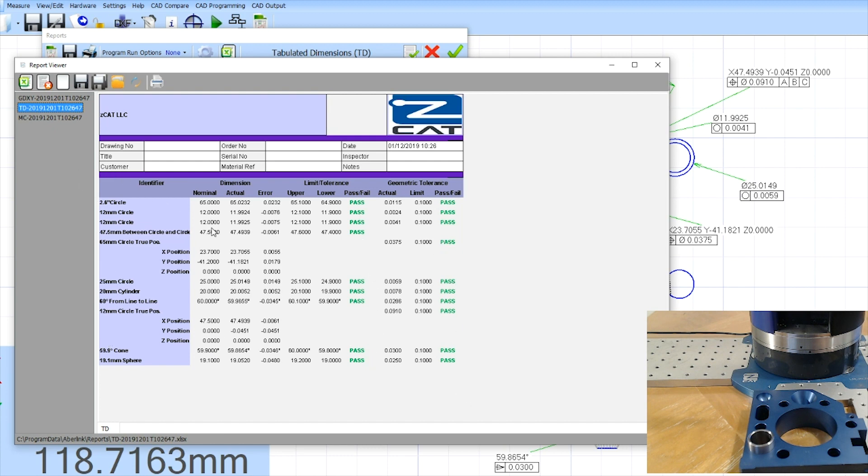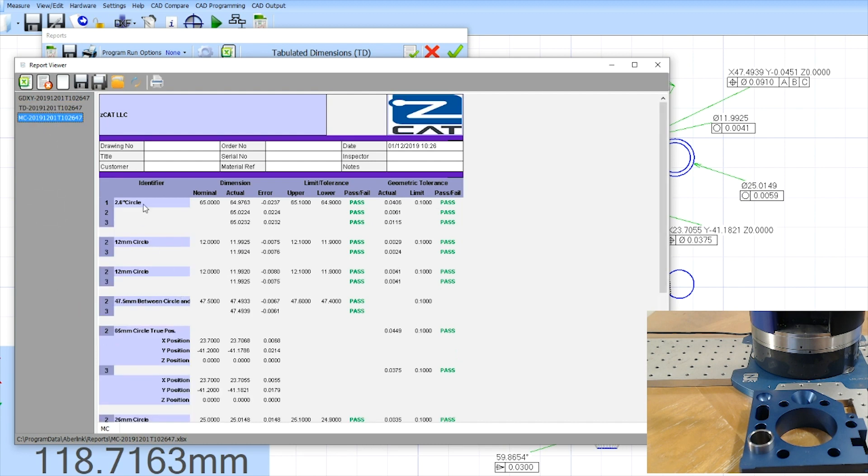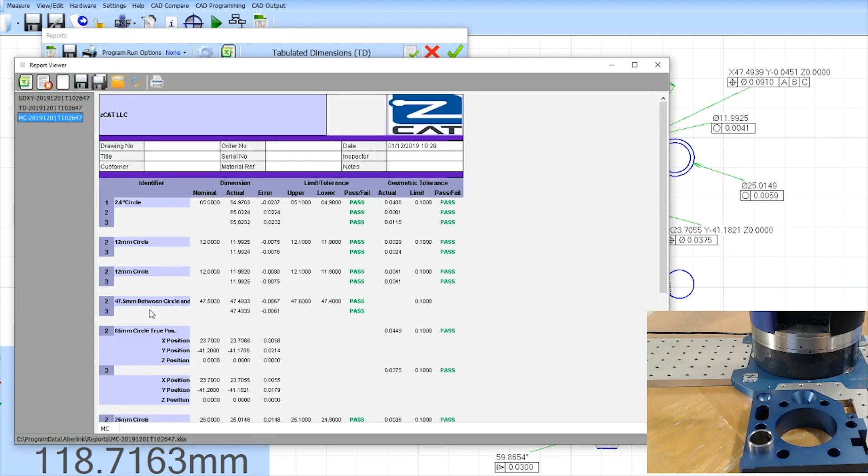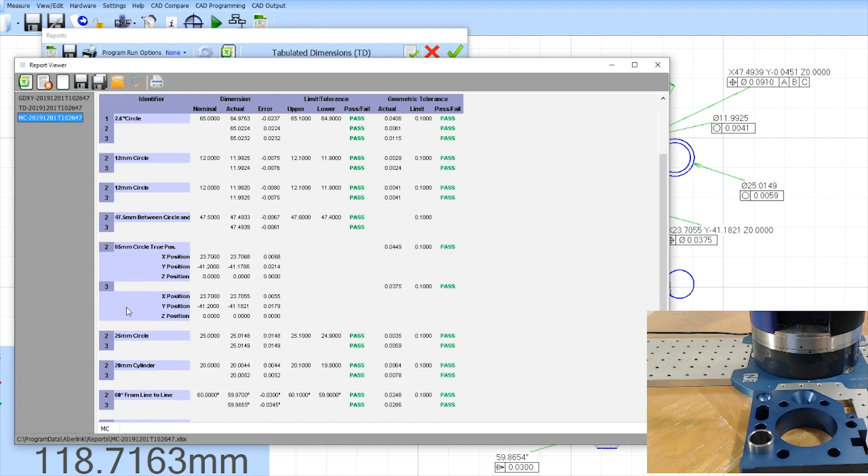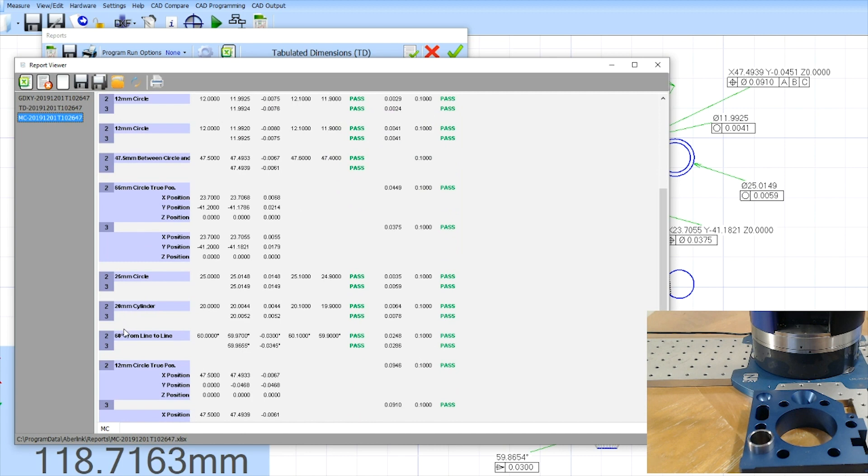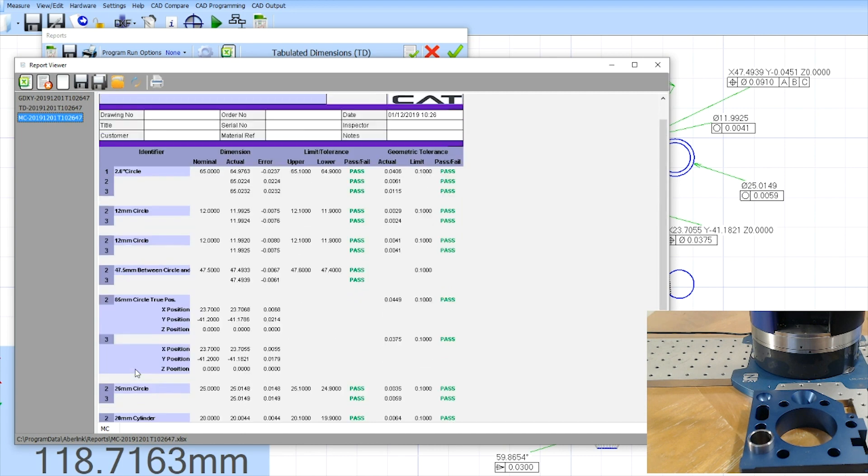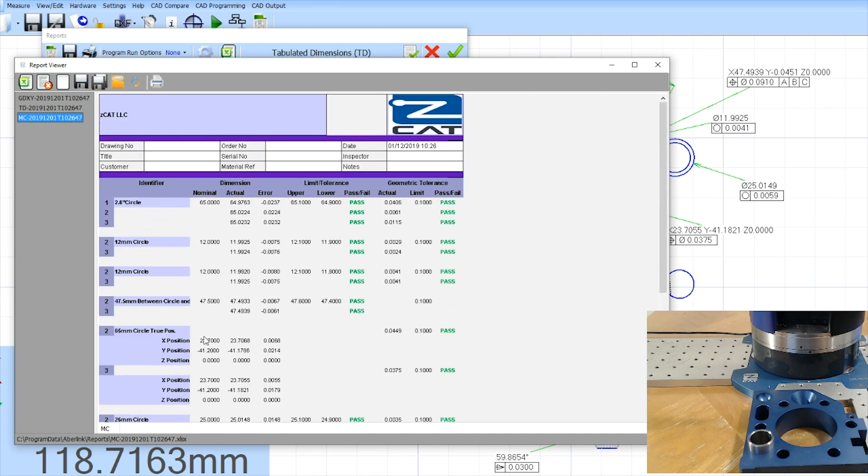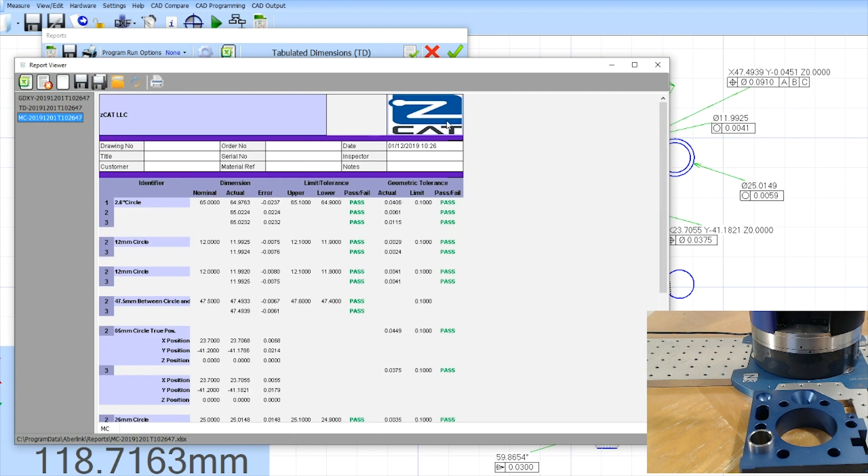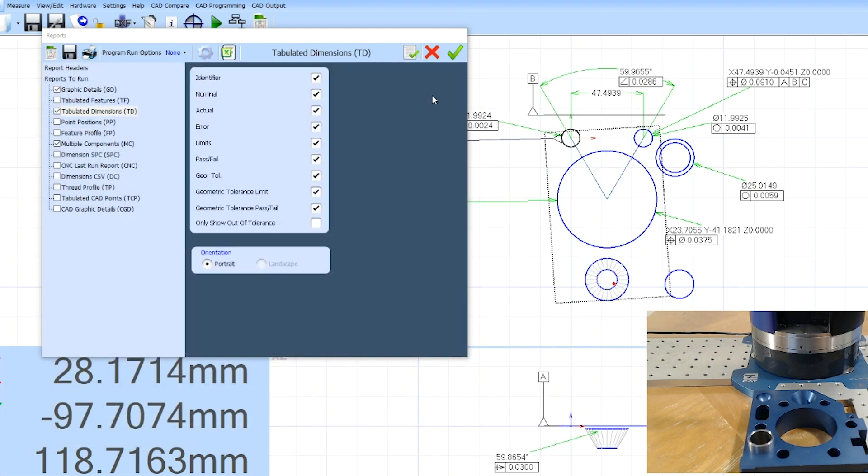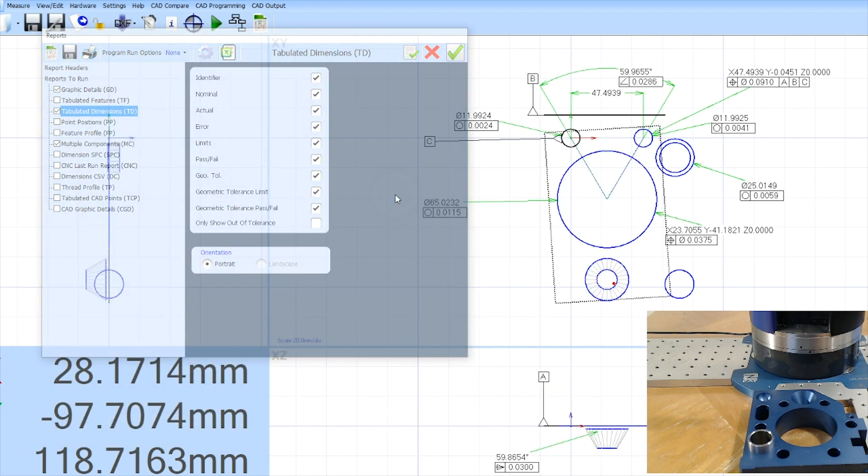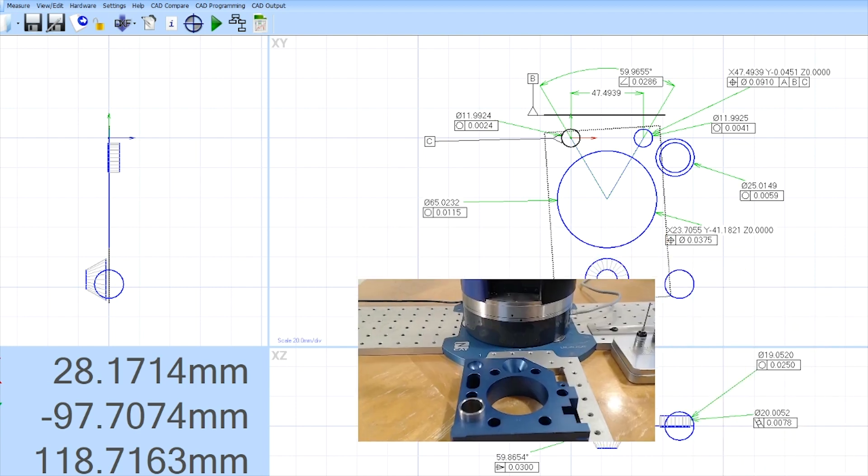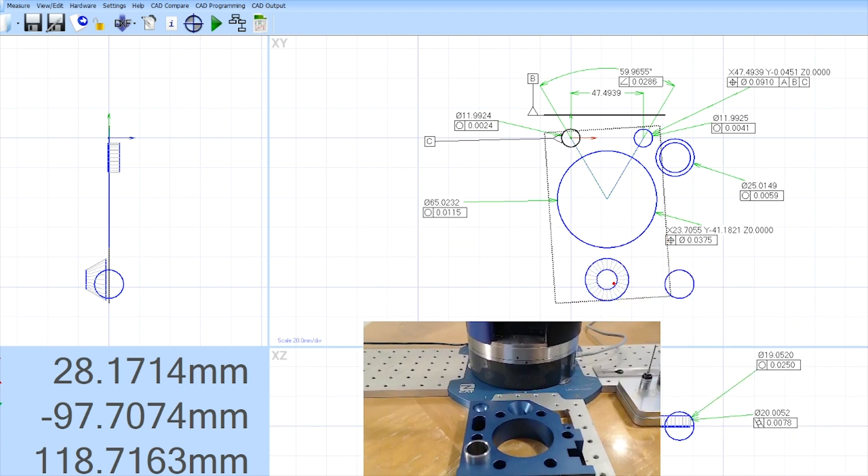If we've run the part more than one time, we can do a multi-component report. And then every time we've run it, it will give us the results for that individual feature. You can see some of them we've run three times, some of them we've only run twice, sometimes we've only run once, but it'll archive the data, and everything is here with a pass or fail. So very quickly, very easily, we can archive the data, we can monitor the results, and we can check the results. So that's how quick and easy we can write a program and run a program on the ZCAT.